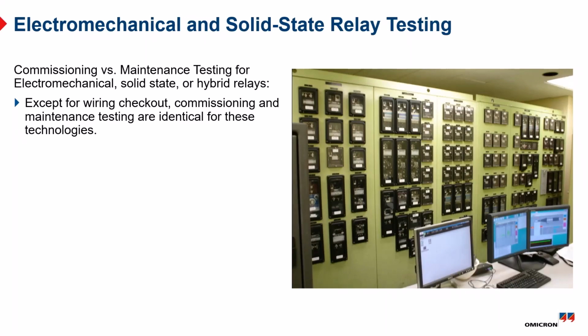Commissioning versus maintenance testing for electromechanical, solid state, and even the hybrid and first generation digital relays, which we call hybrid relays. They usually had an analog back end and then a pretty rudimentary microcontroller on the front end handling the output contacts, the settings, the trip and the communication stuff. So they were kind of half solid state, half digital. That's what we mean by hybrid.